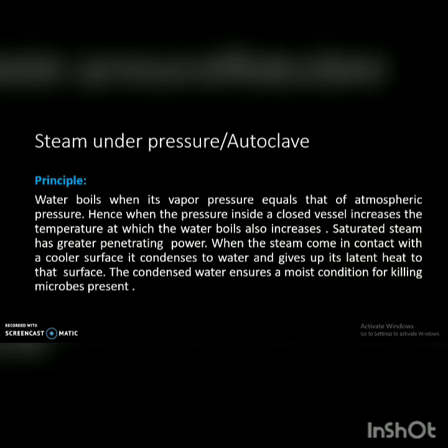Next is steam under pressure or autoclave. The principle is that we all know that water boils when its vapor pressure is equal to that of atmospheric pressure. But when the pressure inside a closed vessel increases, the temperature at which the water boils also increases. The saturated steam has a greater penetrating power, and when the steam comes in contact with a cooler surface, it condenses to water and gives up its latent heat to that surface, and thus the surface is made free of microorganisms.